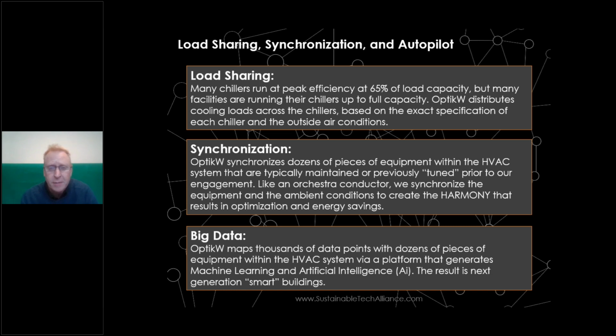With this machine learning, one account up in New England saw that they typically wouldn't have the chillers off except for the dead of winter, like January and February, because the cooling demand was so high for this mixed use laboratory. Within 10 days of the OptiKW system running, they called to ask why the chillers were off, and whether they could be turned back on because something in the algorithm may have gone wrong.